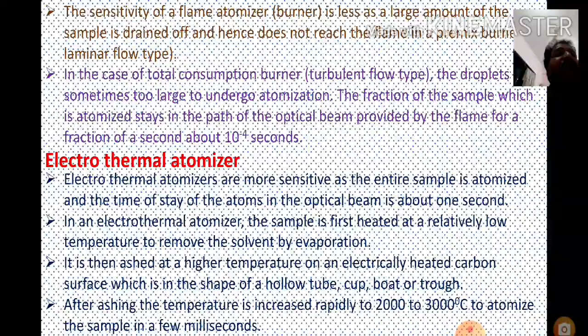In an electrothermal atomizer, the sample is first heated at a relatively low temperature to remove the solvent by evaporation. It is then ashed at a higher temperature on an electrically heated carbon surface which is in the shape of a hollow tube, cup, boat or trough. After ashing, the temperature is increased rapidly to 2000 to 3000 degrees Celsius to atomize the sample in a few milliseconds. The absorption of radiation by the atomized sample can then be measured above the carbon surface.